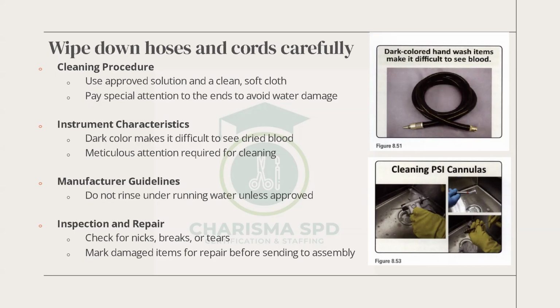Instrument characteristics: dark color makes it difficult to see dried blood. Meticulous attention is required for cleaning. You have to make sure you pay special attention to these things. You cannot overlook anything. Manufacturer guidelines, that's our number one thing. Do not rinse under running water unless approved. Like we had one probe that we used after our end, the Doppler probe. If you rinse it under water, it's going to take you like 2 hours to get it dry.